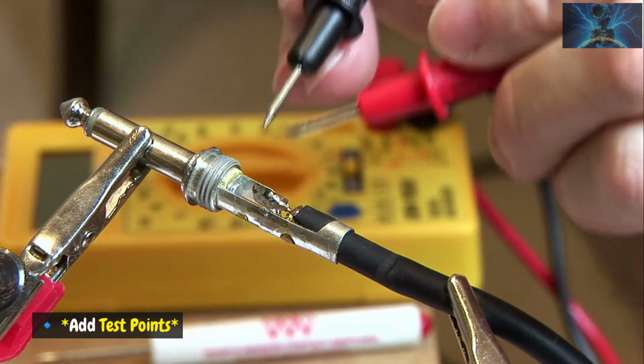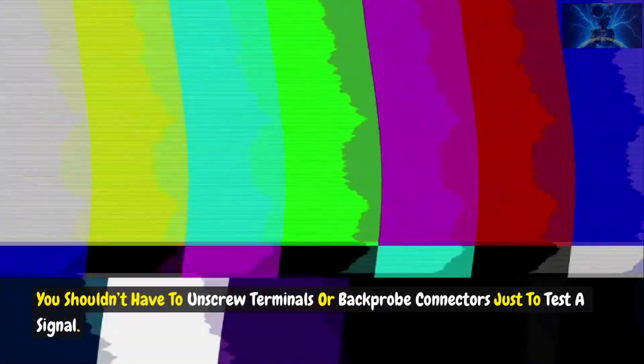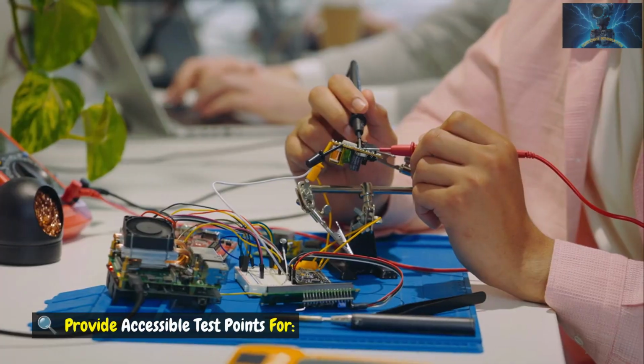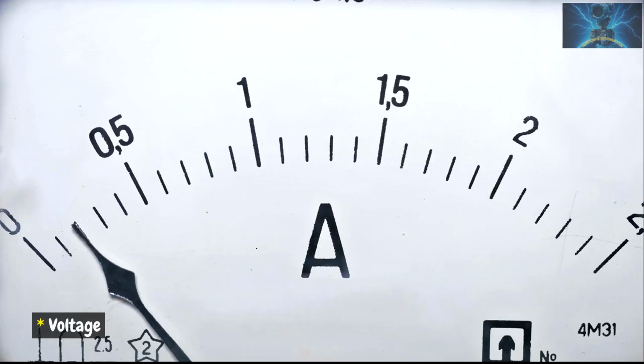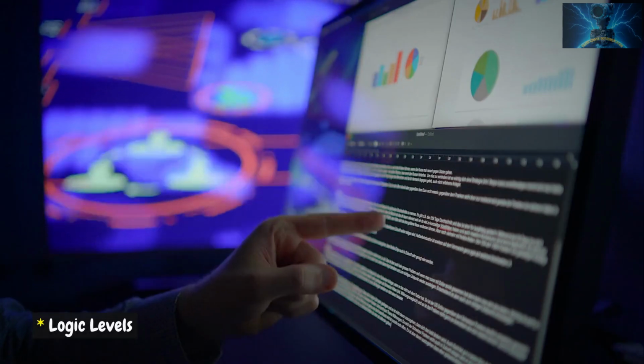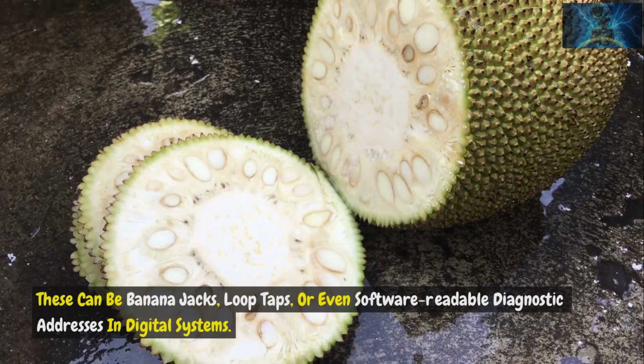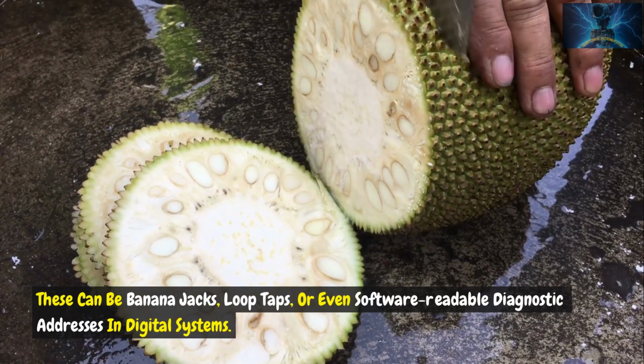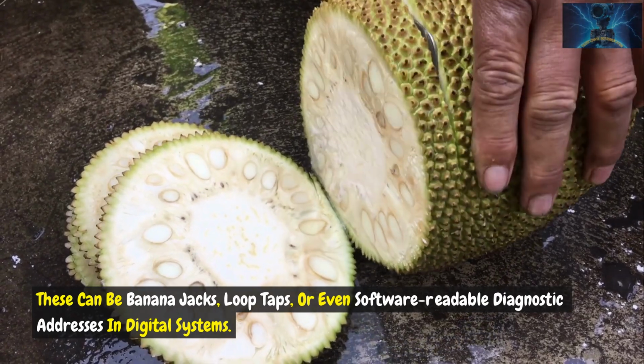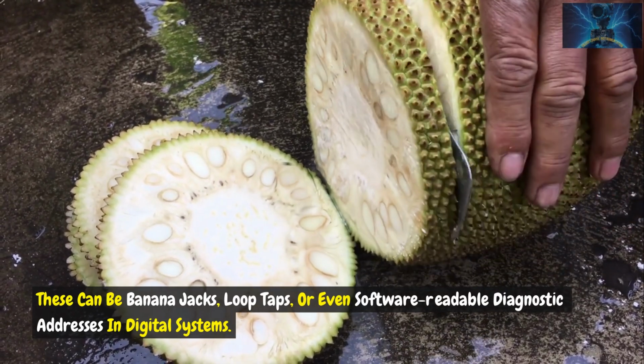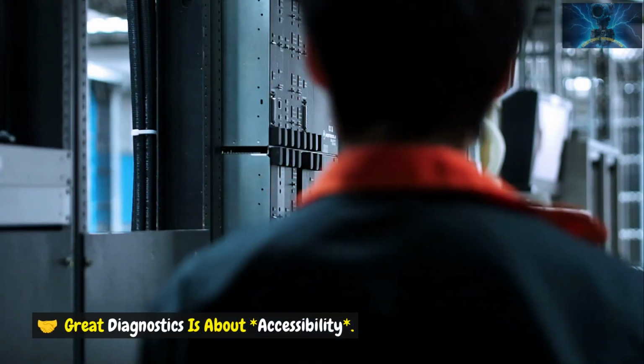Add test points. You shouldn't have to unscrew terminals or backprobe connectors just to test a signal. Provide accessible test points for voltage, current, logic levels, communications. These can be banana jacks, loop taps, or even software-readable diagnostic addresses in digital systems. Great diagnostics is about accessibility.